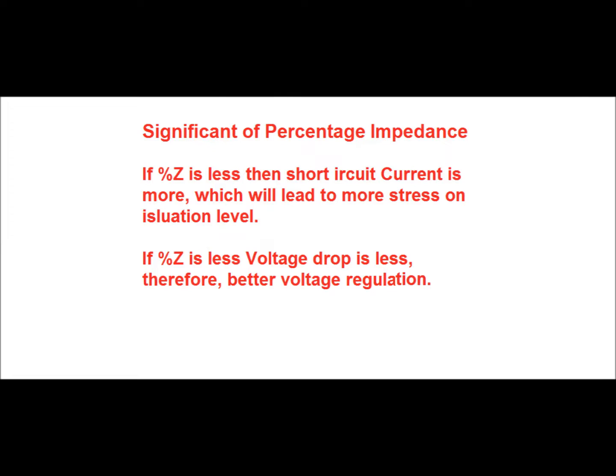What is the significance of percentage impedance of a power transformer? If the percentage impedance is less, the short circuit current will be more, which will produce more stress in the insulation of the power transformer — this is a negative factor. On the other hand, if percentage impedance is lower, it will reduce the voltage drop in the transformer winding, which will facilitate better voltage regulation — a positive factor. Therefore, the percentage impedance must be precisely selected to maintain a proper balance between fault level and voltage regulation.